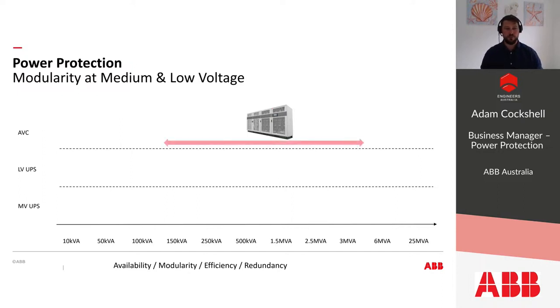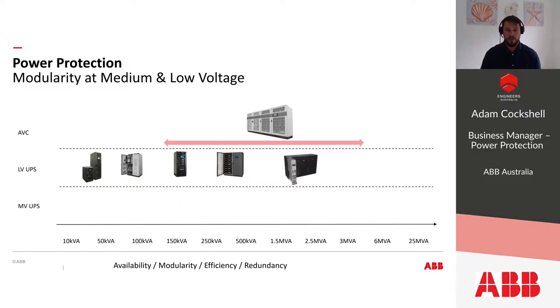When it comes to our DPA UPSs, our DPA UpScale, with 10 and 20 kilowatt DPA UPS modules, is scalable from 10 kilowatts all the way through to 400 kilowatts. Our Powerline DPA, which is our industrial modular UPS, has 20 and 40 kilowatt DPA UPS modules, scalable from 20 kilowatts through to 1.2 megawatts. Our DPA 250S4, with 50 kilowatt DPA UPS modules, is scalable from 50 kilowatts all the way through to 1.5 megawatt. DPA 500, with its 100 kilowatt DPA UPS modules, is scalable from 100 kilowatts through to 3 megawatt. Our Megaflex DPA, with 250 kilowatt DPA UPS modules, is scalable from 250 kilowatt all the way through to 6 megawatt.